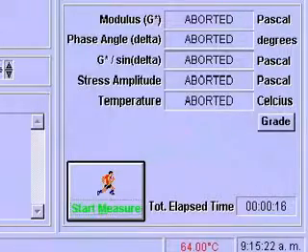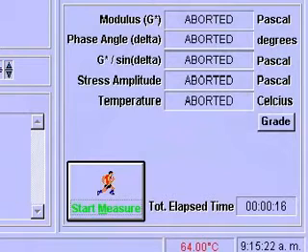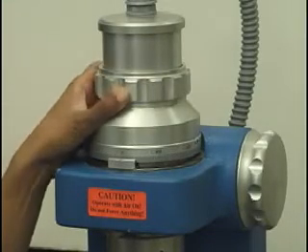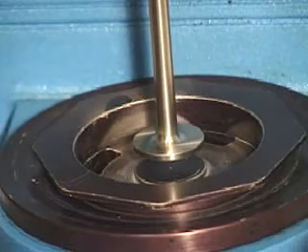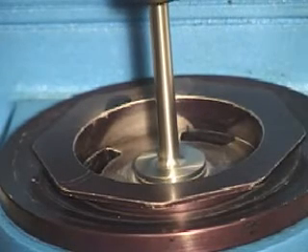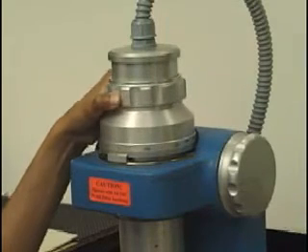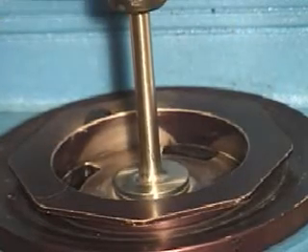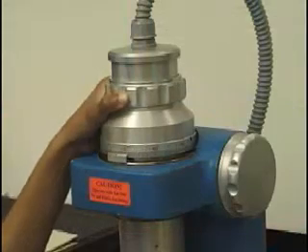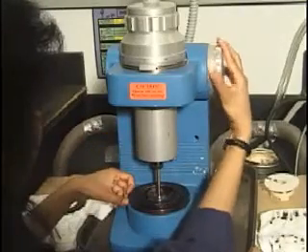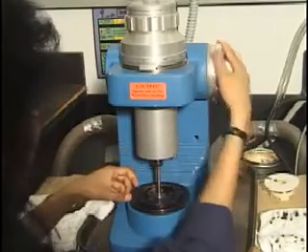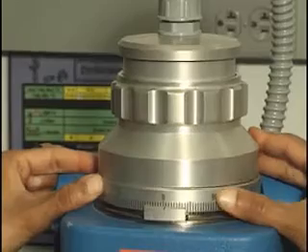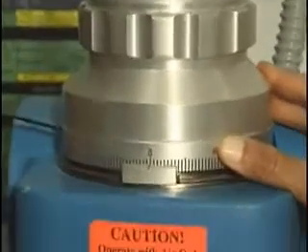After the water bath reaches the test temperature, set the zero gap as shown for older Bohlin DSR models. Newer DSRs have auto gap setting. Rotate the micrometer dial until it points to the zero reading. Spin the spindle and lower the upper shaft all the way down toward the base plate. If the spindle continues to spin, raise the shaft and rotate the micrometer to the left to decrease the gap. If the spindle stops suddenly, raise the shaft and rotate the micrometer to the right to increase the gap. Repeat these steps until the spindle just touches the base plate when the shaft is lowered. This is the zero gap setting. Lock the spindle. Loosen the set screw on the micrometer dial and rotate the dial until the zero coincides with the zero marker. Tighten the set screw at this point.